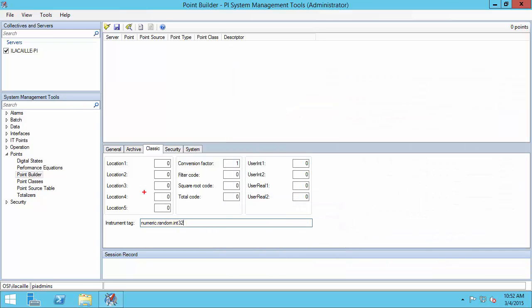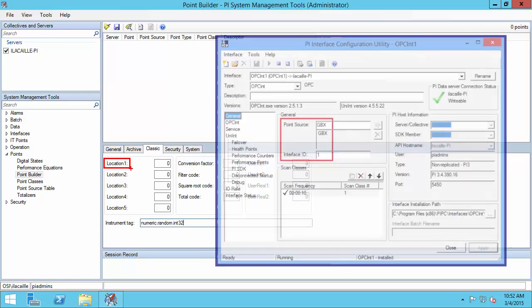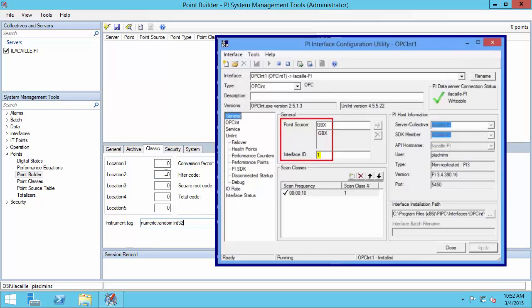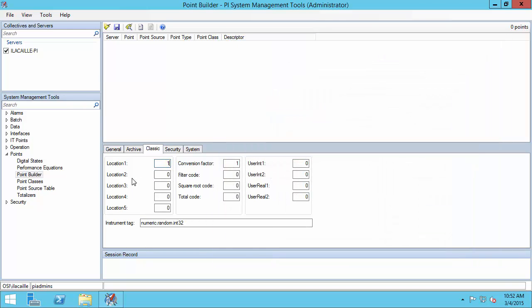The next thing I need to put in is Location 1, which needs to correspond to the interface ID of my PI interface instance. Mine was 1. Next, I need to choose Location 2, which is reserved for special data handling between the OPC server and the PI Data Archive — if some transformation needs to be done, it needs to be specified here. Please check the PI Interface for OPC DA User Guide for more information. I'm not going to use any special data handling, so I'll leave it at 0.